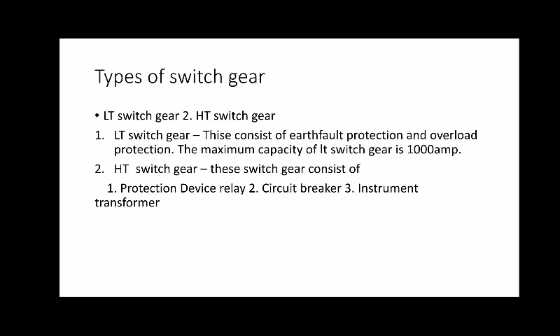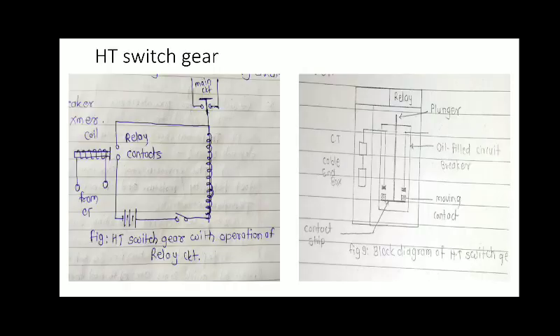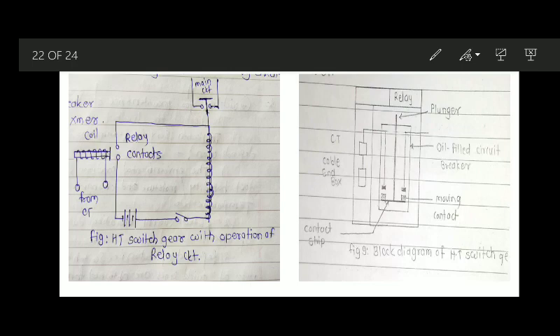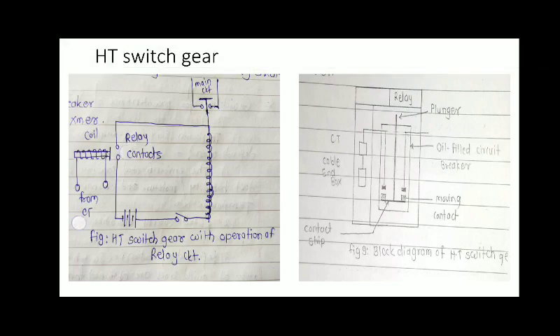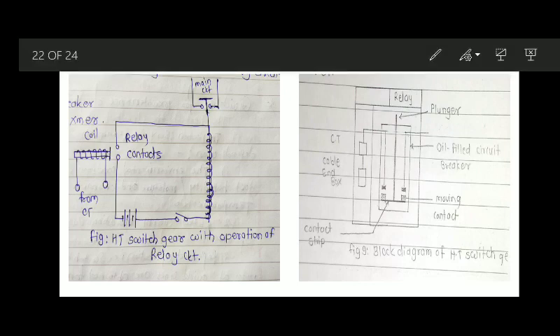Okay, in the next slide it is given the diagram of HT switch gear with operation of relay circuit. So in that diagram, let's see, it is a relay contact. After that, there is a battery. This is a coil. This is from circuit CT. This is from CT, and there is a transformer coil. There is a main circuit. So when the fault is happening, at that situation, this main circuit is tripped, and this makes the relay contacts close, and because of that your circuit breaker is tripped. So this is a HT switch gear.